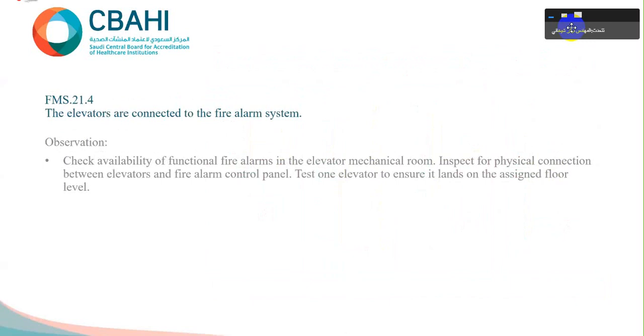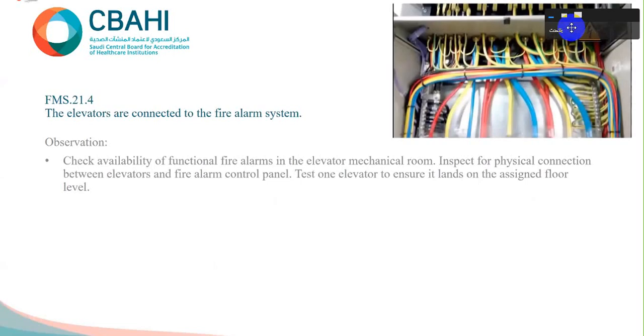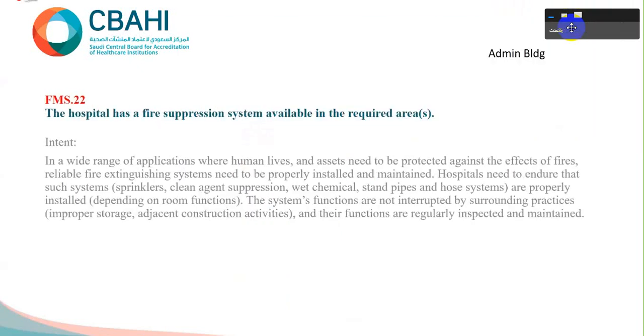And we should visit the elevator room to make sure that the elevator control box has the cable connected here and labeled fire alarm system. It's connected to the control panel of the elevator. And please keep in mind, elevators cannot be used during fires unless otherwise fire rated, and the shaft of the elevator is separated from the main building, and the cables should be fire rated as well. We have some hospitals in the kingdom where elevators can be used during the fire and are usually dedicated for civil defense uses, especially in medical cities. The hospital has a fire suppression system.